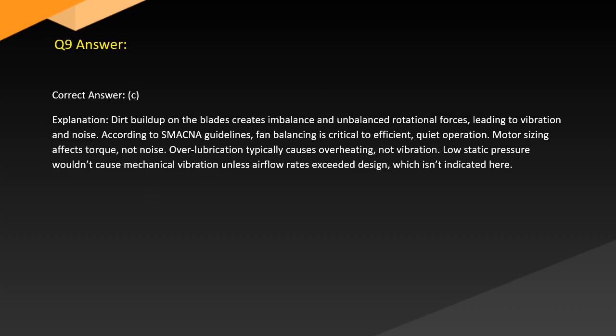Answer. Correct answer: C. Explanation. Dirt buildup on the blades creates imbalance and unbalanced rotational forces, leading to vibration and noise. According to SMACNA guidelines, fan balancing is critical to efficient, quiet operation. Motor sizing affects torque, not noise. Overlubrication typically causes overheating, not vibration. Low static pressure wouldn't cause mechanical vibration unless airflow rates exceeded design, which isn't indicated here.